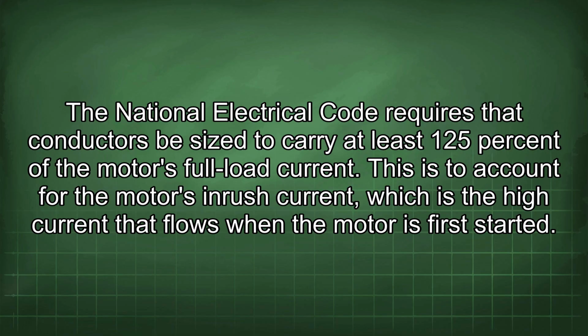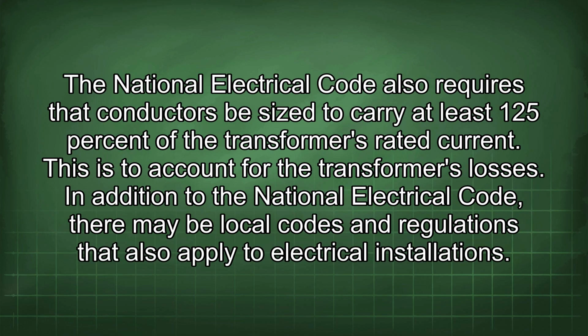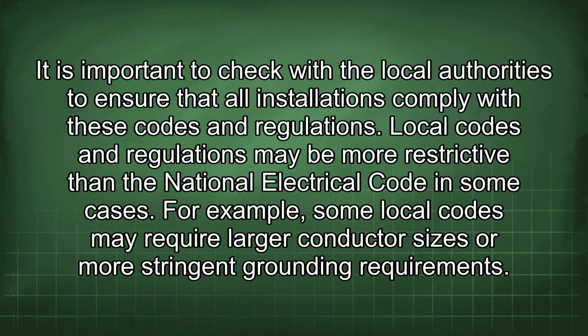This is to account for the motor's inrush current, which is the high current that flows when the motor is first started. The National Electrical Code also requires that conductors be sized to carry at least 125% of the transformer's rated current. This is to account for the transformer's losses. In addition to the National Electrical Code, there may be local codes and regulations that also apply to electrical installations. It is important to check with the local authorities to ensure that all installations comply with these codes and regulations.